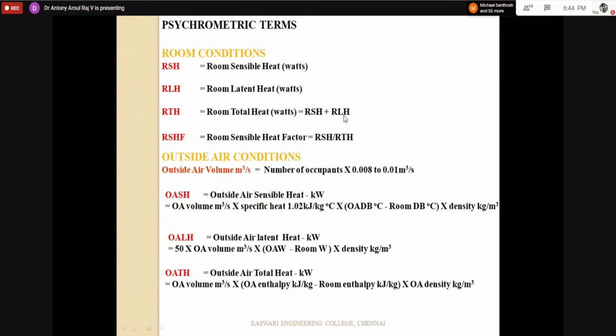And we are taking outside air. Why are we taking outside air? Because we have occupants inside the room. Each of them has to breathe and requires oxygen. There is a minimum standard by which we have to supply it. For example, 10 cfm per person. That means if 4 persons are there, I have to give 40 cfm. Like that I have to multiply. So the quantity of air which I am taking inside depends on the number of occupants.